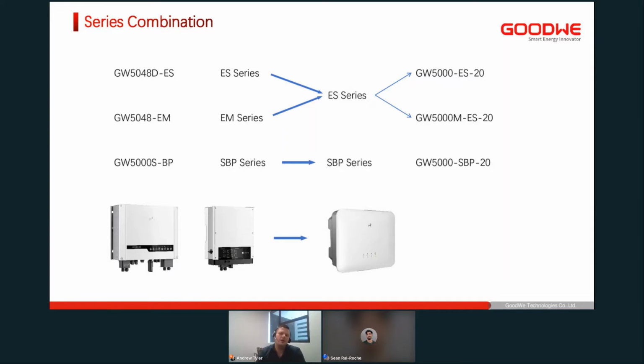So for the 5 kilowatt example, you would see the part number as GW5000M-ES-20. And then for the higher backup capacity ES product, you would see a similar part number, just with the M missing. And that would mean that a 5 kilowatt inverter has a 5 kilowatt backup. So it's a much higher capacity backup, which might be more suited to markets that have common grid failures or load shedding, as we know it well in South Africa.